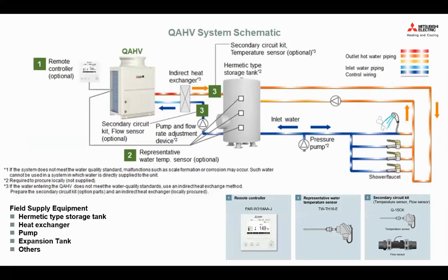So here is the typical schematic we recommended or suggested. Of course, the possibilities are endless depending on how you wish to do it. Because for QAHV, simply put, cold water goes in, hot water comes out, and then you can utilize that hot water. It can be bringing it from 10 degrees C all the way to 80 degrees C, or 21 degrees C all the way to 65 degrees C. Right, 15 degrees C all the way to 60, 65, depending on your usage.